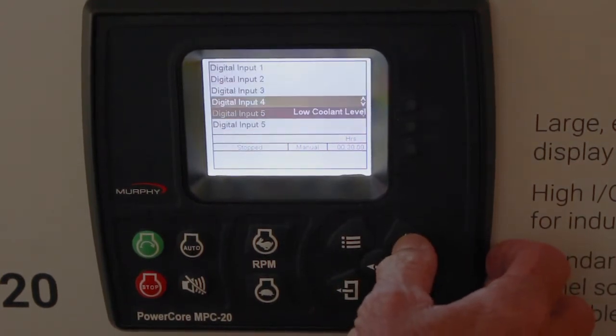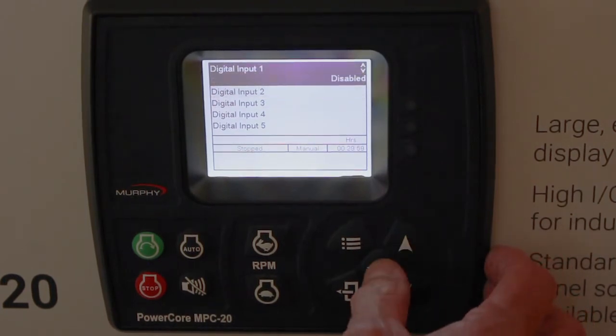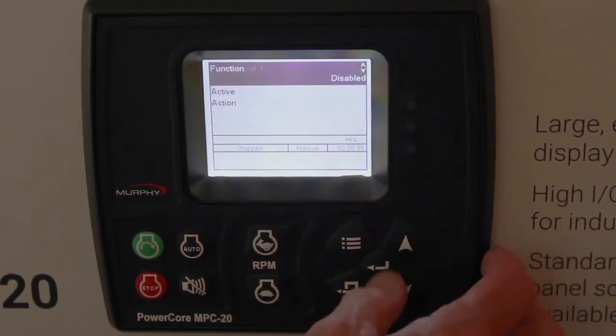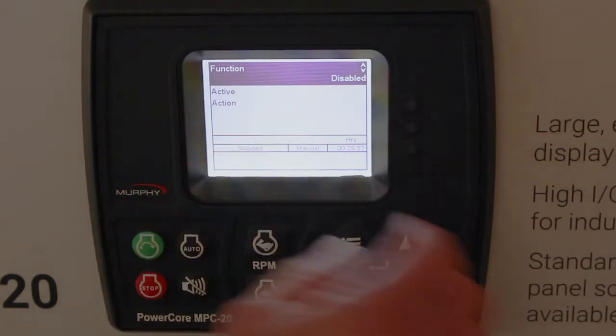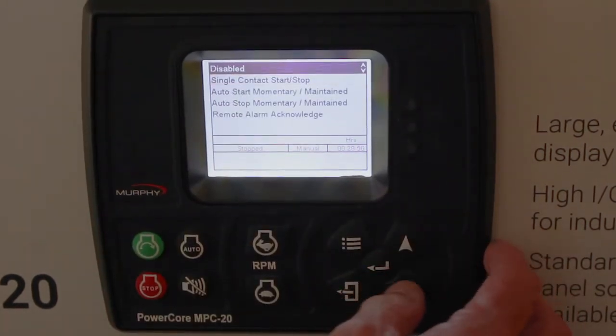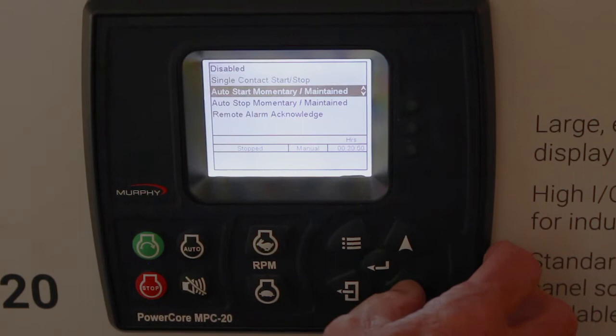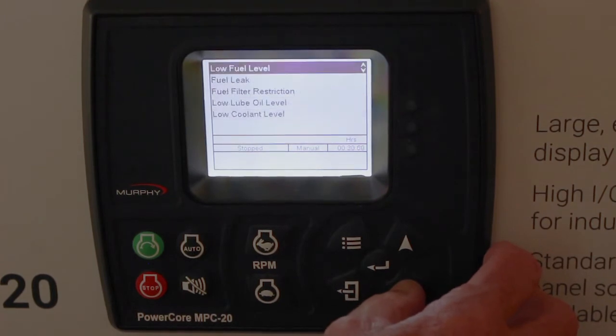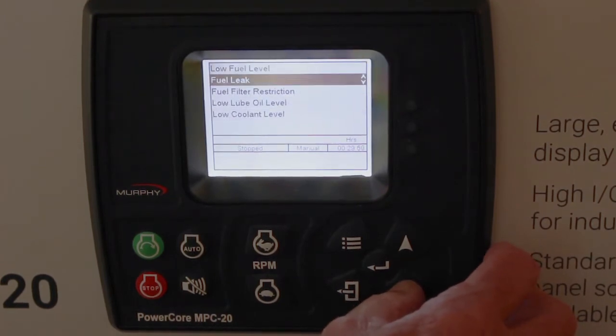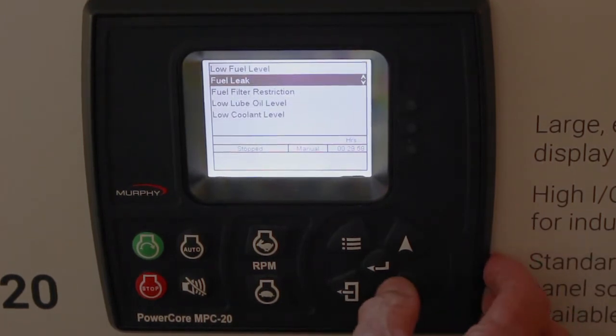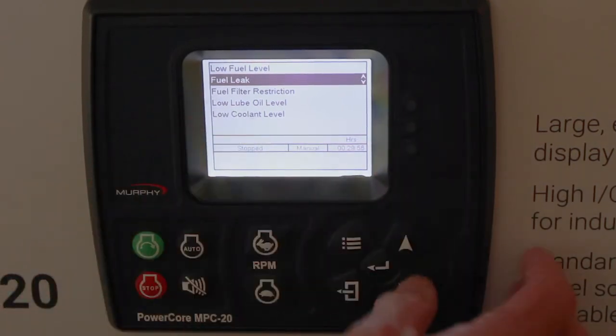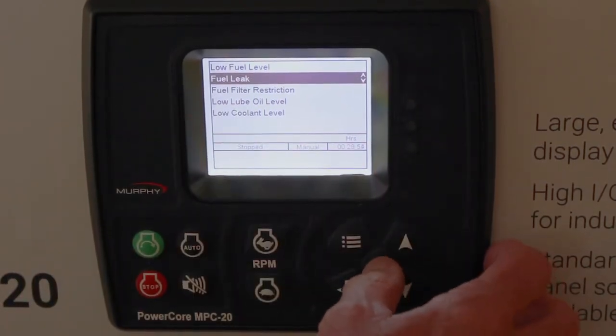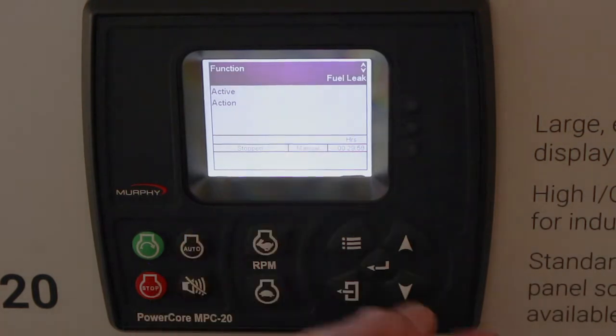Let's change one just so you get an idea. Digital input one is disabled — the function is disabled. Hit enter and there's a menu in here. Let's choose a fuel leak, which will be shown on the display if this input goes active. Hit enter — fuel leak.